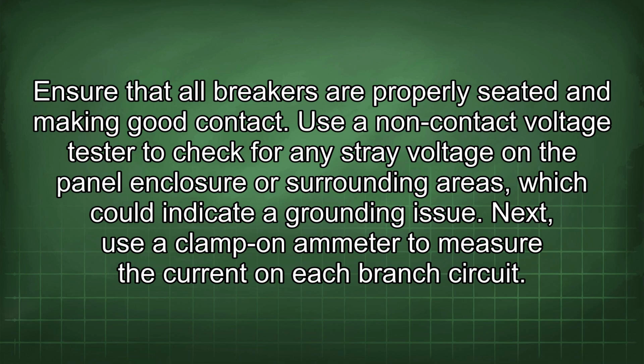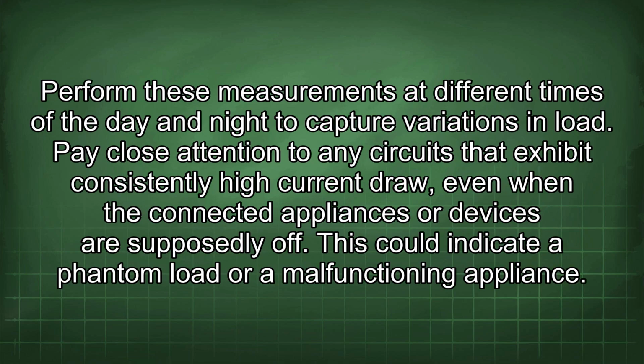Next, use a clamp-on ammeter to measure the current on each branch circuit. Perform these measurements at different times of the day and night to capture variations in load. Pay close attention to any circuits that exhibit consistently high current draw, even when the connected appliances or devices are supposedly off. This could indicate a phantom load or a malfunctioning appliance.